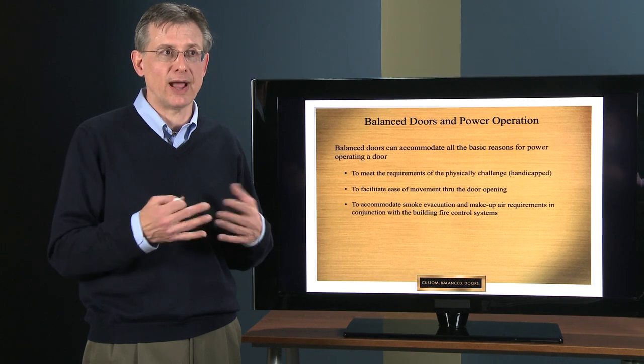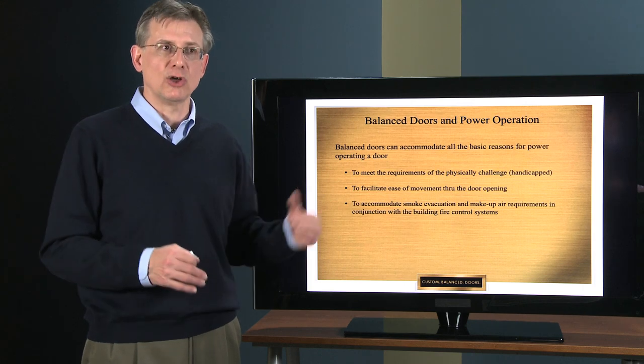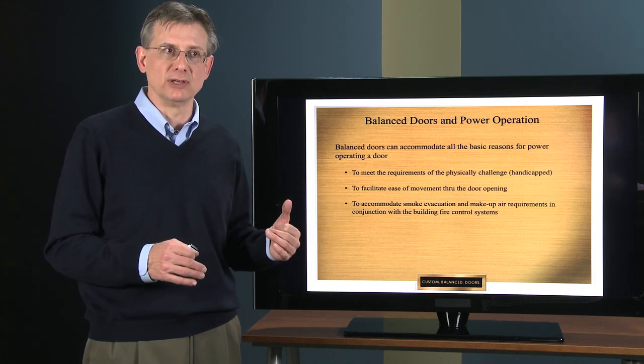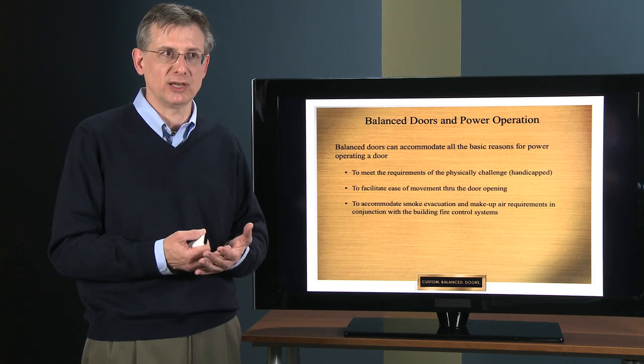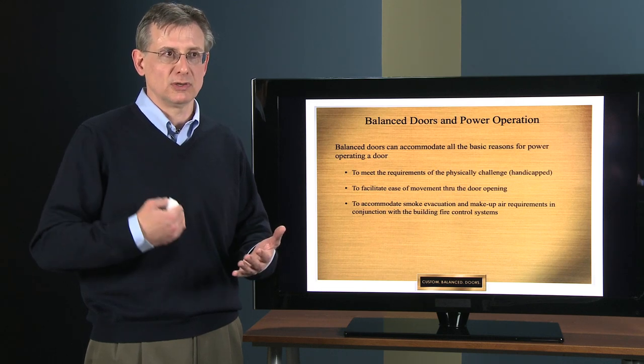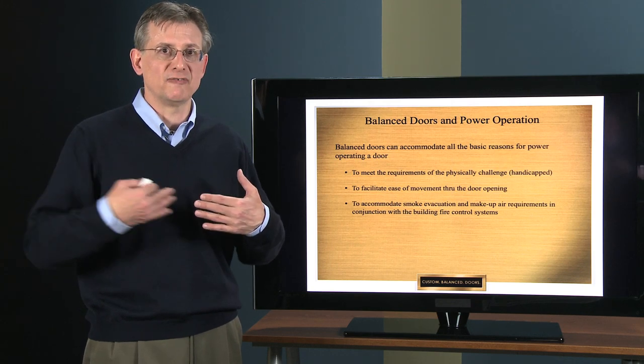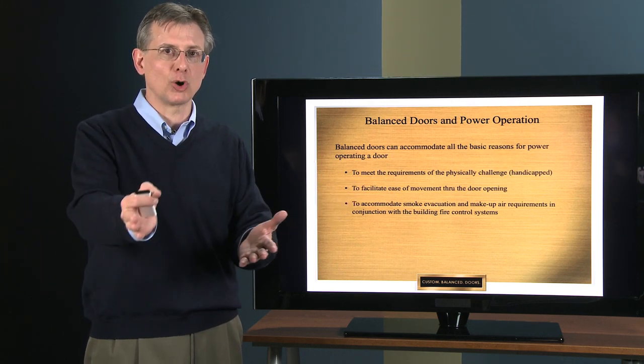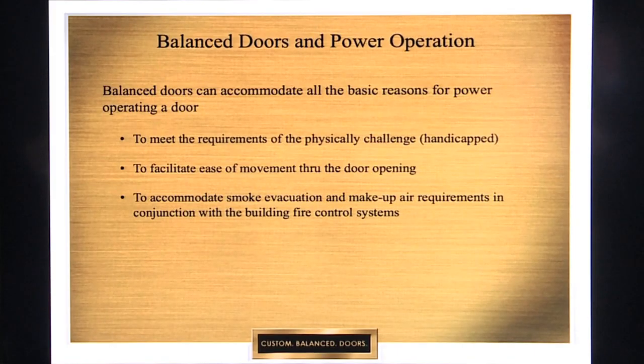That operator could be used for the physically handicapped via a push button. It also can be hooked up to the fire control system pull stations, so that when somebody does initiate the fire alarm, whether it be a pull station or a security desk, that same operator or other operators on other doors will fire open, push that door open to 90 degree hold open, and stay there for an indefinite period of time until reset, doing the smoke evacuation and make-up air requirement.